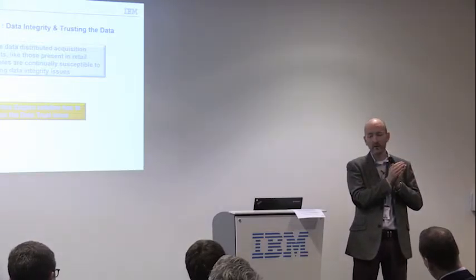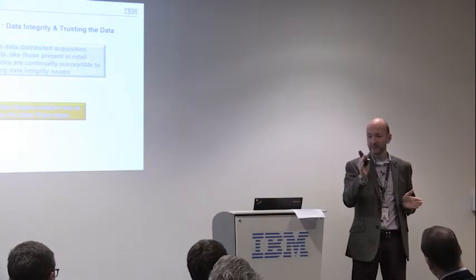But supposing you're missing data over a month because the alerting wasn't working, or you were ignoring the alerting, you may not want to just say, well, here's the reading here, here's the reading, and every day it's just incrementally increasing. You might want to look at a previous month, or a previous month from the same year, and use the profile of that for the interpolation. So it becomes more meaningful. So in the evenings, we don't use as much power, and in the days, we use a lot more power.